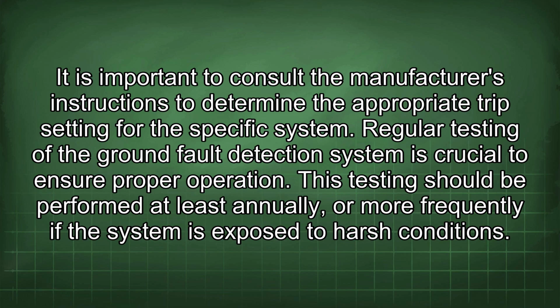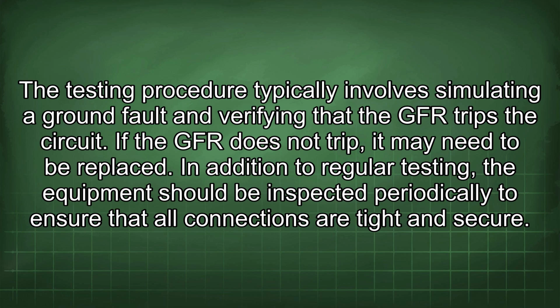Regular testing of the ground fault detection system is crucial to ensure proper operation. This testing should be performed at least annually or more frequently if the system is exposed to harsh conditions. The testing procedure typically involves simulating a ground fault and verifying that the GFR trips the circuit. If the GFR does not trip, it may need to be replaced.